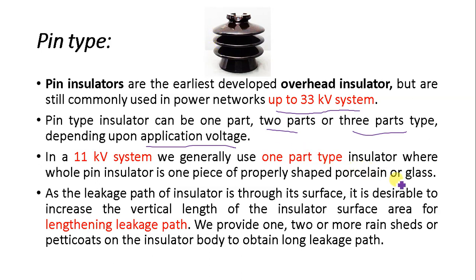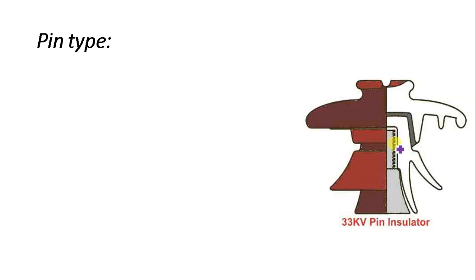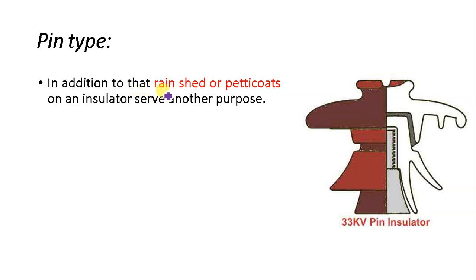Since the leakage path of the insulator is through its surface, it is desirable to increase the vertical length of the insulator to lengthen the leakage path. To achieve this, we provide one, two, or more rain sheds — also called petticoats — on the insulator body to obtain a longer leakage path. In the figure you can see one, two, and three rain sheds or petticoats.